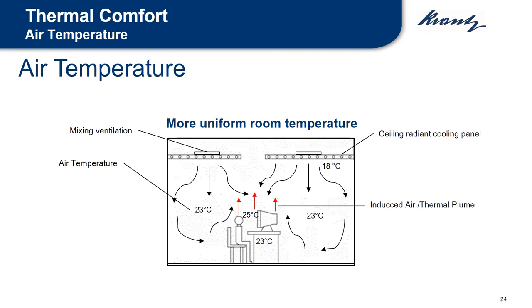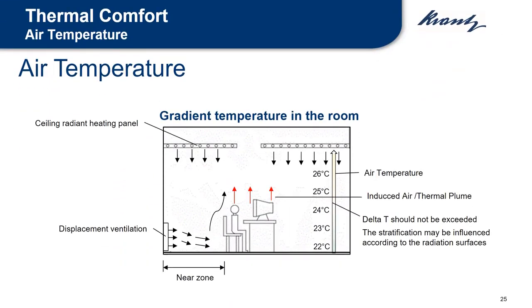With turbulent mixing ventilation and a chilled ceiling operating in cooling mode, the limits for vertical temperature gradients are of no significance, as the related values are always far below these limits. With displacement ventilation and a chilled ceiling operating in heating mode, however, one should take care that the limits for vertical temperature gradients are not exceeded.